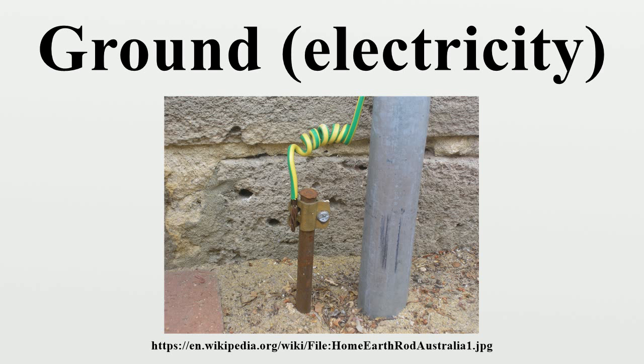dangerous touch voltage. Electronics. Signal grounds serve as return paths for signals and power within equipment, and on the signal interconnections between equipment. Many electronic designs feature a single return that acts as a reference for all signals. Power and signal grounds often get connected, usually through the metal case of the equipment.